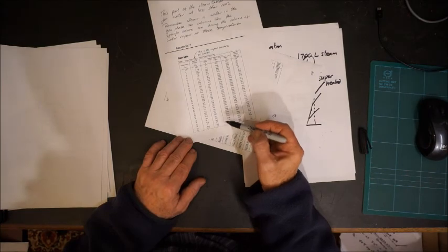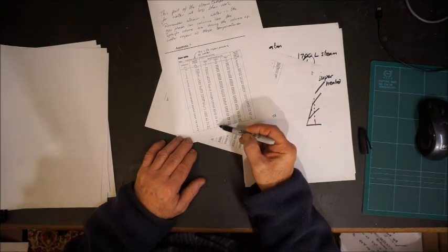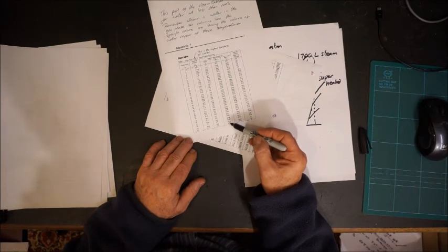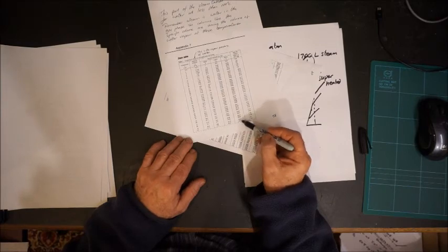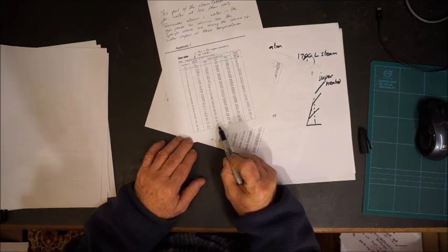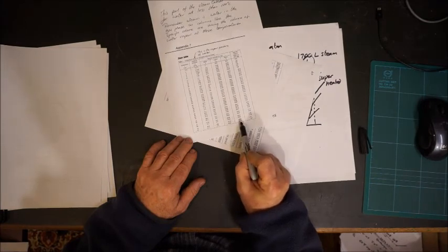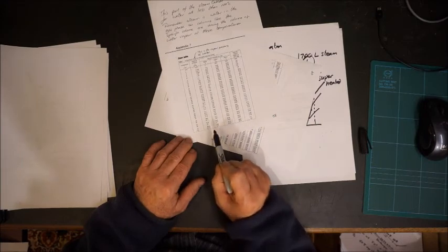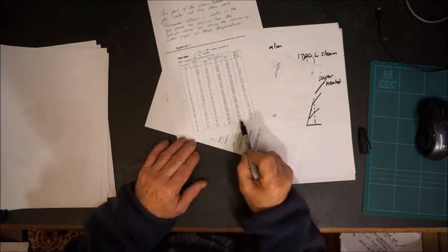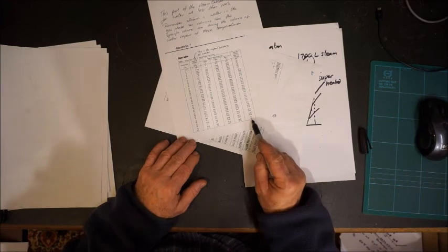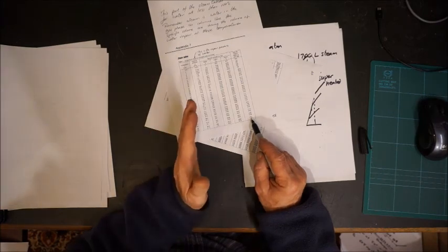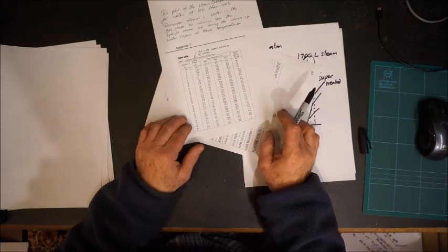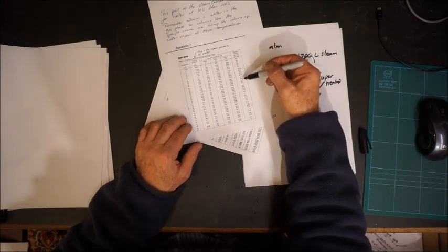If you started off with water at 0 degrees, that's the amount of energy required to heat it to 100. This is the amount of energy required to heat that 100 degree water to 100 degree steam. This number here is the sum of this one plus this one. This is saying this much energy has been needed to turn a kilogram of water at 0 degrees all the way to a kilogram of steam at 100 degrees. And this is the specific volume. So this is 1.67 cubic meters per kilogram of water, which is around about 1,700 liters. At lower pressures, the volumes get much bigger.